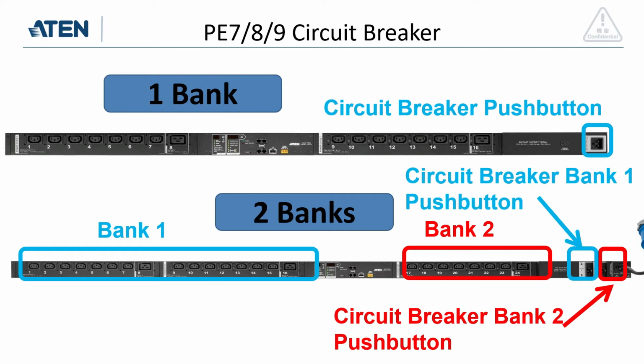So if one of the servers creates a short circuit, the entire bank is going to go down. In the upper product, we only have one bank, so the entire PDU goes down until you press this button, which is your safety mechanism.